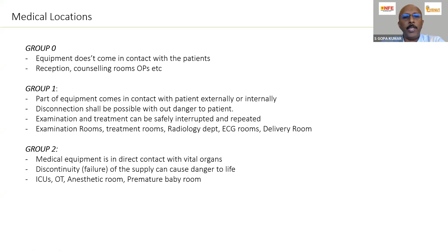The most critical ones are group 2 medical locations, where medical equipment is in direct contact with vital organs, meaning the medical equipment or conductive fluids bypass the skin, sometimes in touch with the heart. Even a very small voltage could be fatal. So with respect to criticality, these three groups are specified: group 0, group 1, and group 2 location.